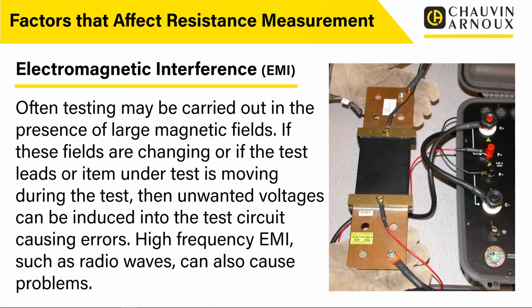Now, electromagnetic interference, or EMI. Often testing may be carried out in the presence of large magnetic fields. That's no surprise, as electricians generally operate in the presence of large magnetic fields. That could be cables with currents travelling down them, where we've got a large magnetic field around them. It could be transformers, it could be motors, it could be all sorts of things where we've got these large magnetic fields.